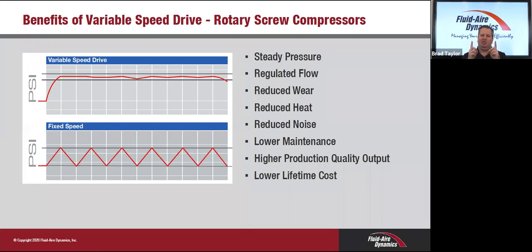During that period of time that the machine is running unloaded, it's essentially sitting there spinning, doing absolutely no work. That's the wasted energy that you're referring to, and being able to vary the speed to match the demand avoids it. Those other advantages just naturally come along with it, such as reduced wear, reduced maintenance, reduced noise, reduced heat, all those things you were just discussing. Great point. The other advantage with modulation is you get a steady pressure output. Some customers have told us it gives a better product output, because that compressed air is used whether it's screen printing or moving product out of a die, and when it has a steady pressure, they get a better quality output, or they could run their processes at a faster speed.